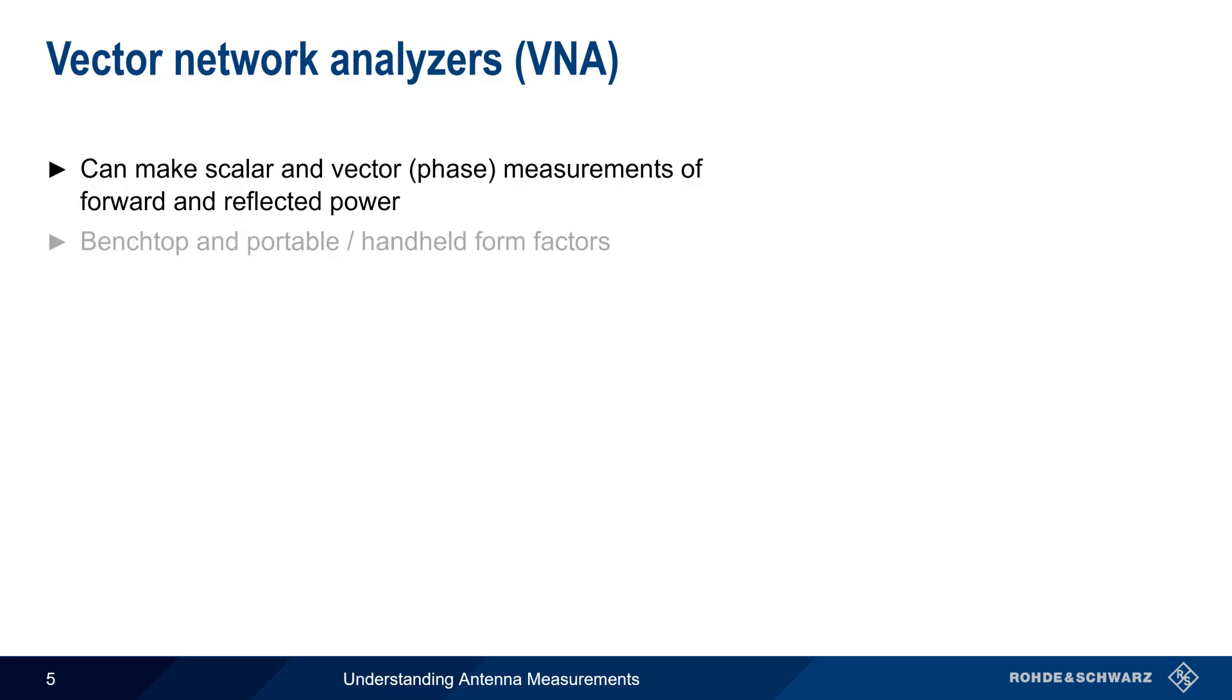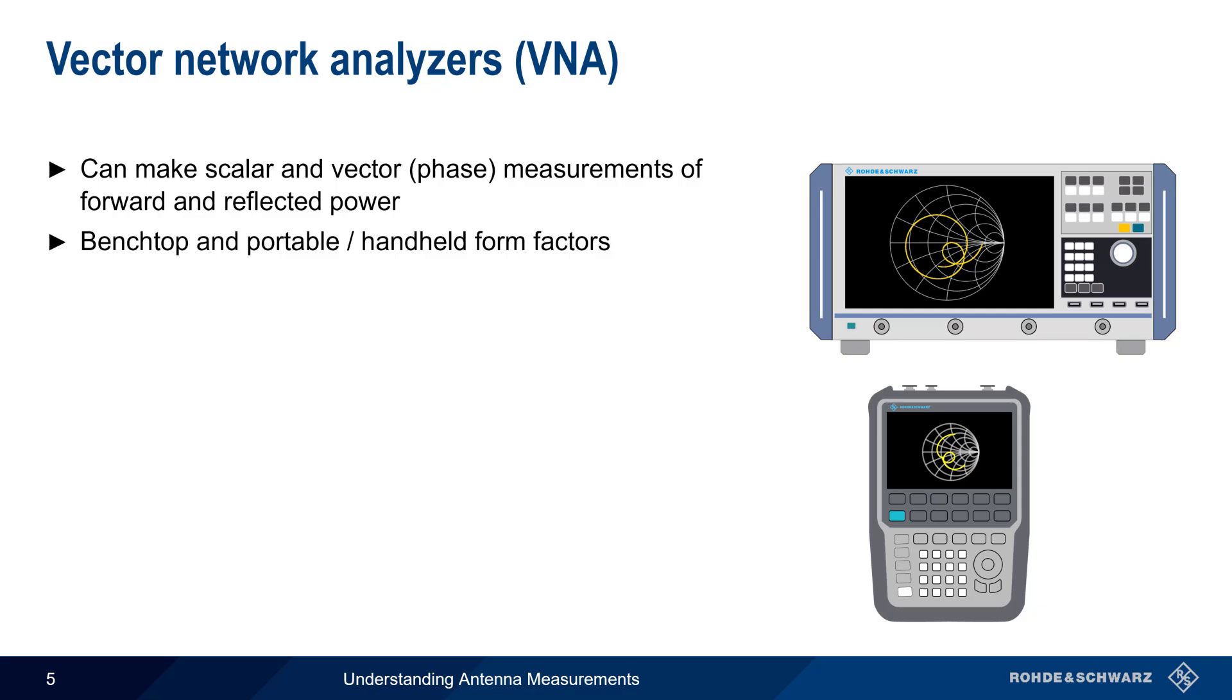Vector network analyzers can make scalar and vector measurements of both forward and reflected power, and they're available in both benchtop and handheld form factors. Modern VNAs have a wide frequency range, usually up to single or double-digit gigahertz, and they also have a high dynamic range. In addition, VNAs support various calibration procedures, which enables very high measurement accuracy and repeatability.